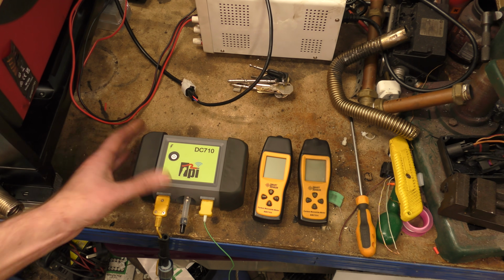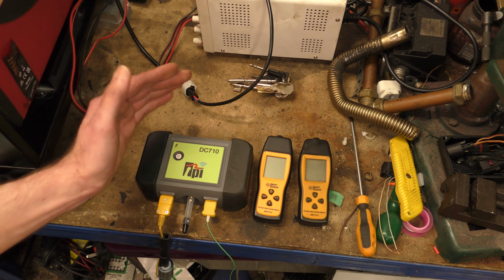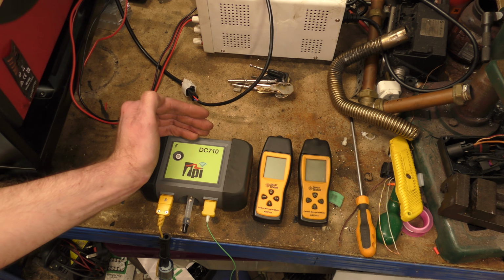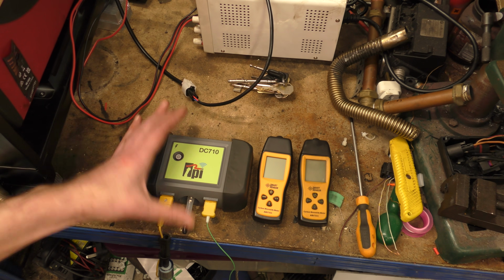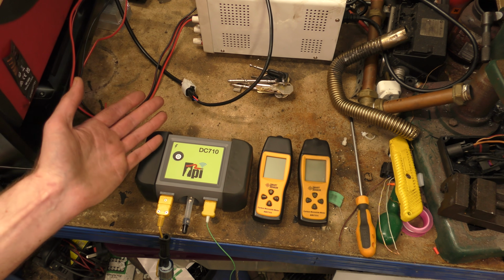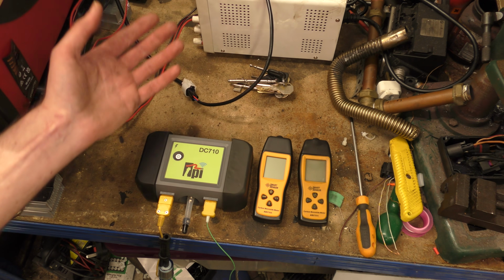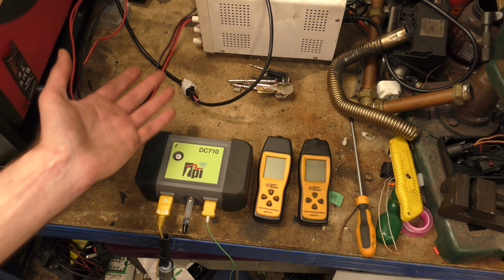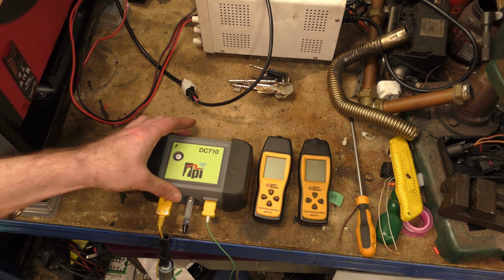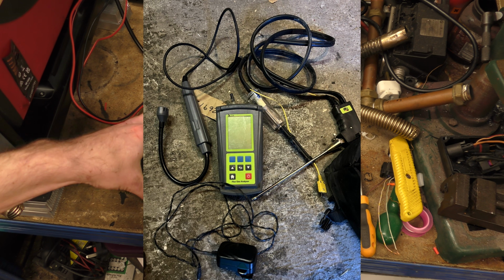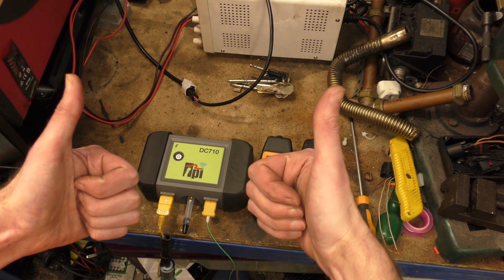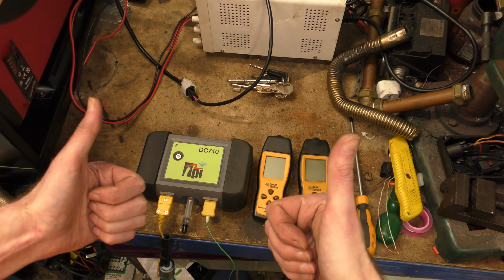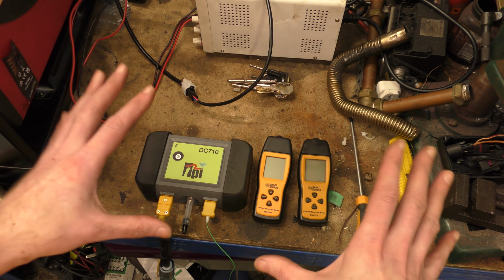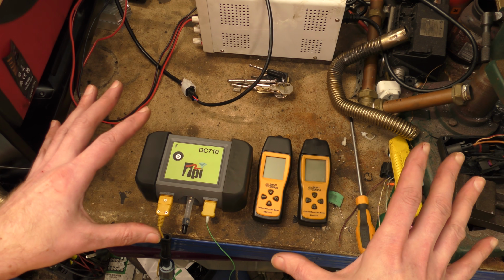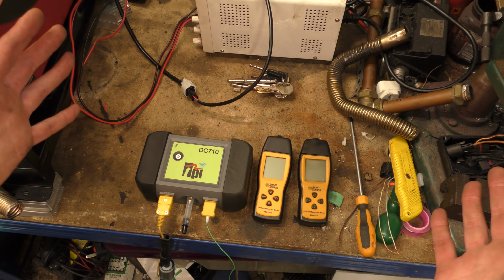And I'm going to tell my story about the TPI here. So I wanted a combustion gas analyzer. And as you do, well, for me, I don't need it to be calibrated. I'm not a central heating engineer or a gas boiler fitter. I could do with a second-hand one. So I went on eBay and I purchased the TPI 716 from a seller. He said it was in good working order, just needed calibrated. Now I'd looked at a few meters, and some of them, once they're out of calibration, they don't work. They just cease to exist.